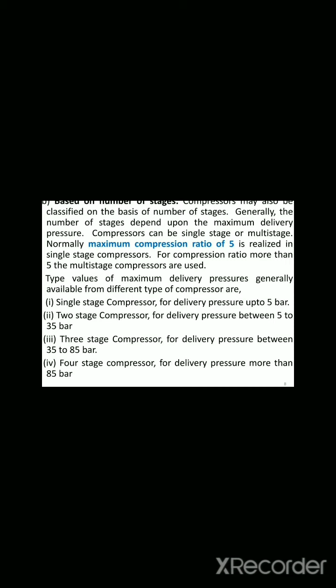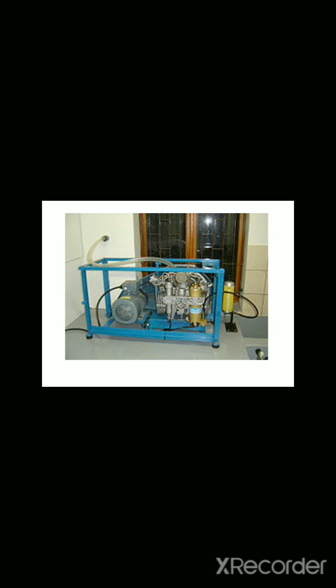This is a picture of a multi-stage air compressor and where it is going to be used. At that time, the air compression stages are going to be more than 2 or 3, and the air is compressed and delivered at a higher pressure, meaning above 85 bar. At that time, this multi-stage air compressor is going to be used.